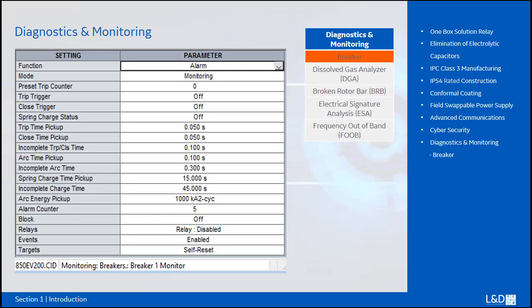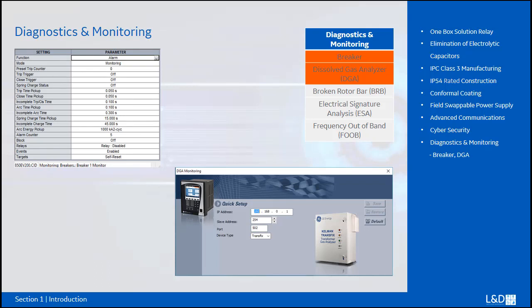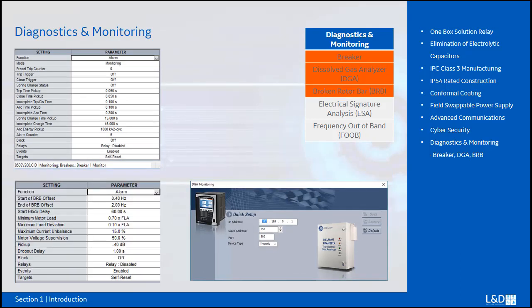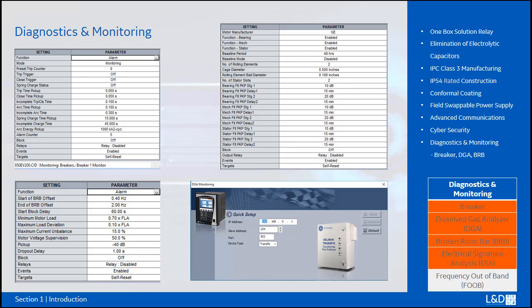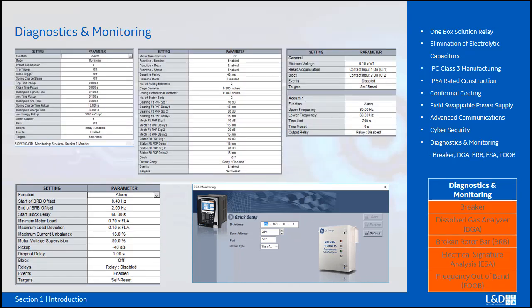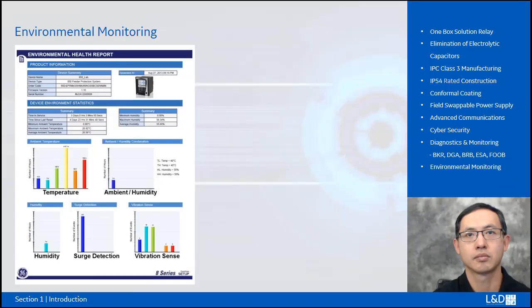8 Series integrated asset monitoring and diagnostic makes a proactive approach towards asset management rather than a reactive one. Advanced diagnostic and monitoring for breaker health is available for all 8 series relays. And dissolved gas analysis for the transformer, broken rotor bar for the motor, and also ESA, electrical signature analysis for the motor, and last but not least, frequency out-of-band monitoring for the generator. Monitored environmental conditions include temperature, humidity, and transient voltage.